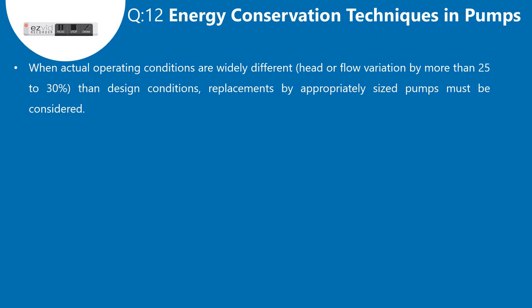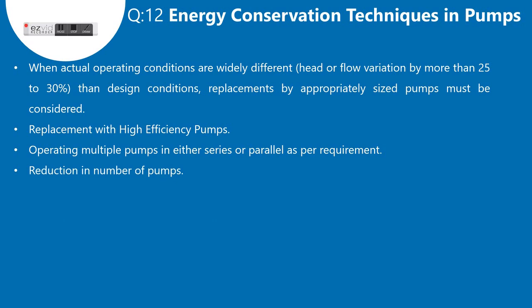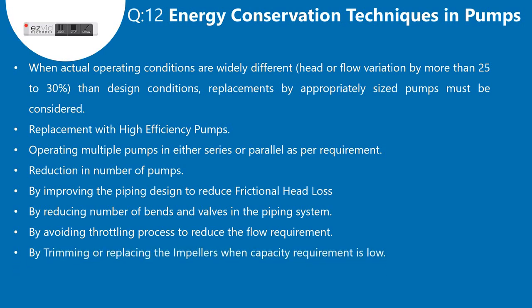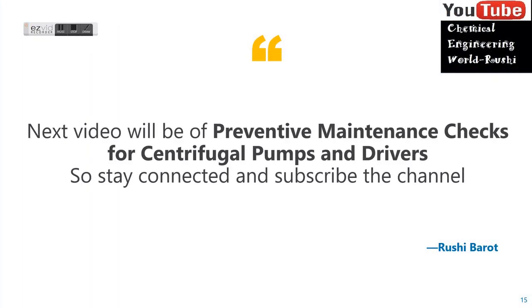Question 12: Energy conservation techniques in pumps. When actual operating conditions are widely different — head or flow variation by more than 25 to 30 percent from design conditions — replacement by appropriately sized pumps must be considered. Other techniques include: replacement with high efficiency pumps; operating multiple pumps in series or parallel as per requirement; reduction in number of pumps; improving piping design to reduce frictional head loss; reducing number of bends and valves; avoiding throttling to reduce flow; trimming or replacing impellers when capacity requirement is low; using variable speed drives; and using energy efficient motors.